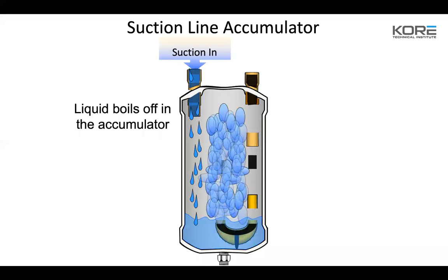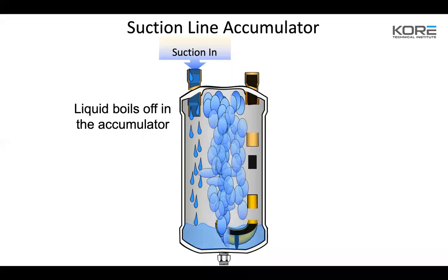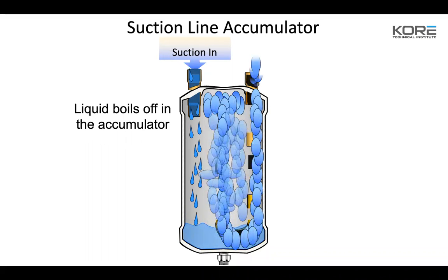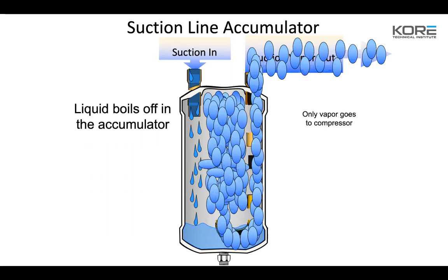Or melt it off. Go ahead. What's causing it to ball up in ice? Is it too much refrigerant in it or what? No, it's an outdoor unit. Yeah, it's too much refrigerant. So they're there for a reason. I mean, if they're icing up or frosting, that's normal. They're supposed to do that.